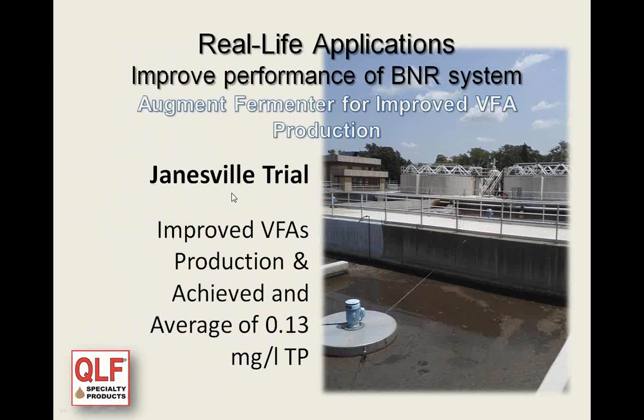Okay, augmenting a fermenter to improve volatile fatty acids production. Did that at Janesville, and we were able to achieve an average 0.13 milligram per liter total phosphorus.